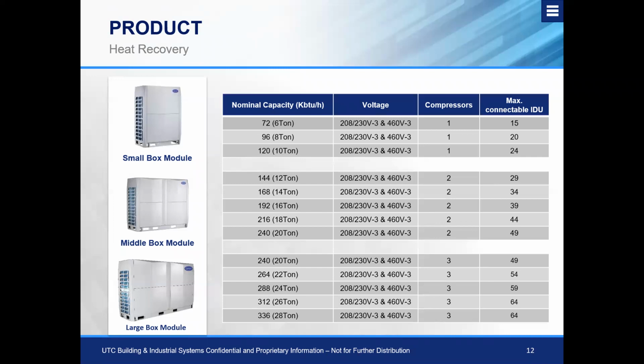So as we increase to the middle box module, this will range from 12 all the way up to 20 tons. And now we're adding 2 compressors in. So we're going to get a little bit greater efficiency because we have that second compressor, and that also adds some redundancy. And just like we had on the small box module, as we increase in tonnage, our total maximum connectable indoor unit quantity will increase as well.